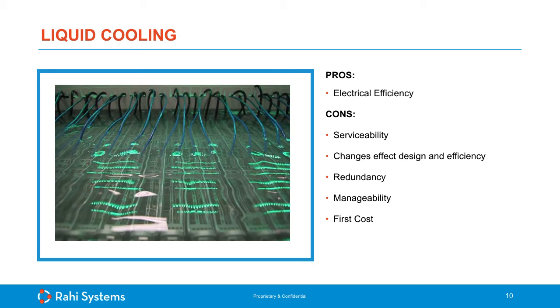The challenge in many cases is obviously the maintenance and serviceability issues of the servers and the cooling system. Also, in many cases, they may be considered not redundant, because it's really tough to design it as an N+1 or a 2N design. So there are some challenges there from a redundancy standpoint. But they have a really good electrical efficiency, so their operating cost is much lower. However, the first cost would be considered pretty high in comparison.